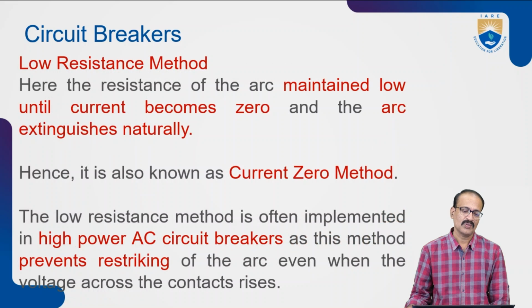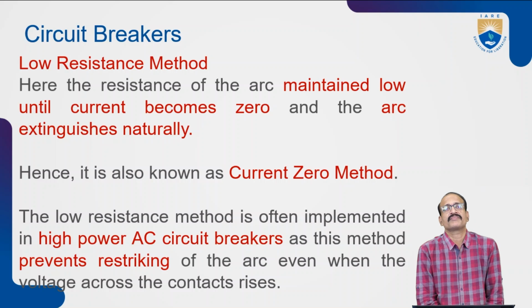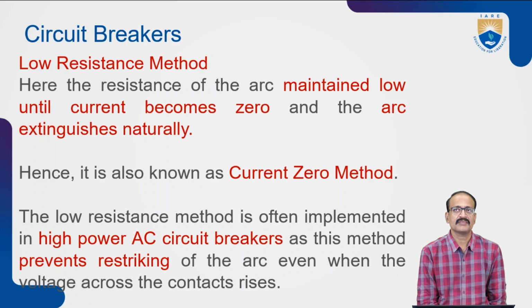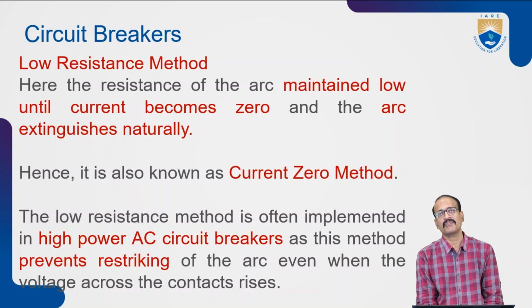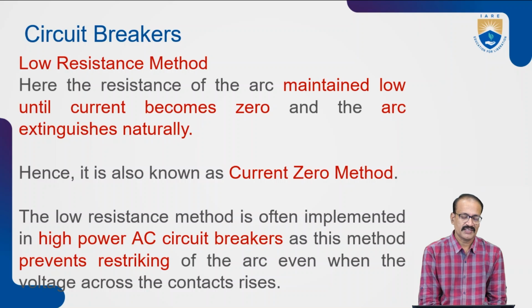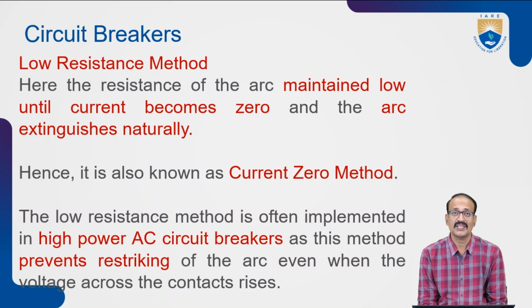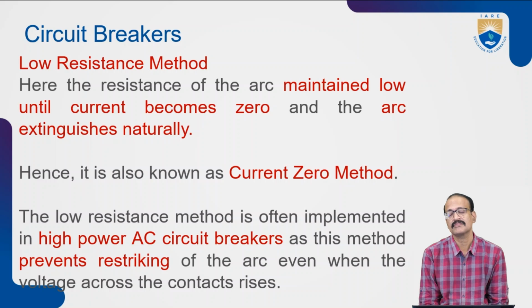So another method is the low resistance method. Here we are waiting for the current to get extinguished naturally. That means here the resistance of the arc is maintained low. So we are not opposing, we are allowing low resistance until the current becomes zero. That's why it is also called the zero current method.